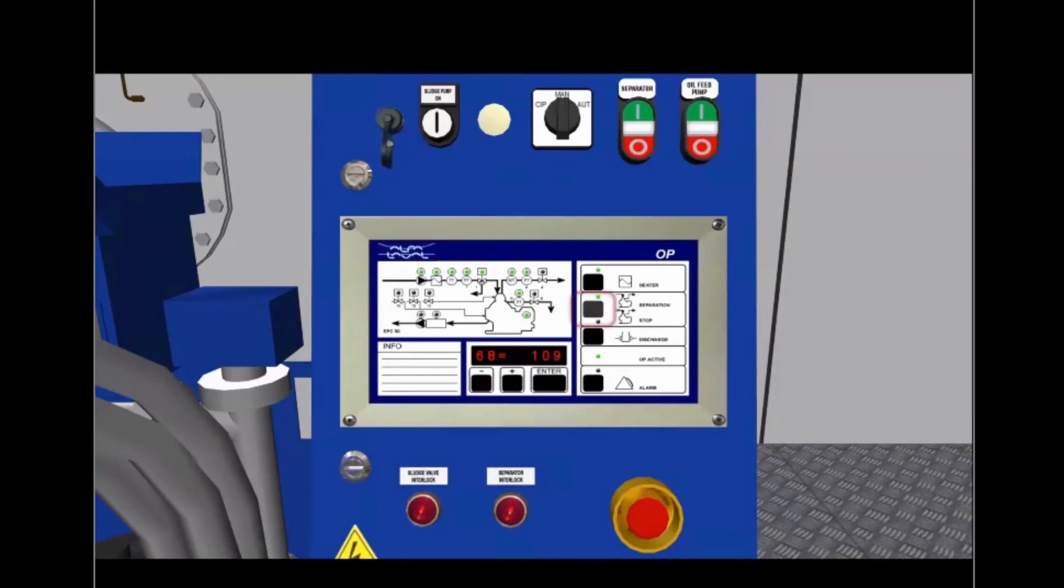To stop the system, push the separation button on the operator panel. The yellow LED for the separator stop sequence starts to flash. A sludge discharge is initiated. The stop sequence LED changes to steady yellow and the green LED for separation system operation goes out. When the sludge discharge is completed, stop is displayed.